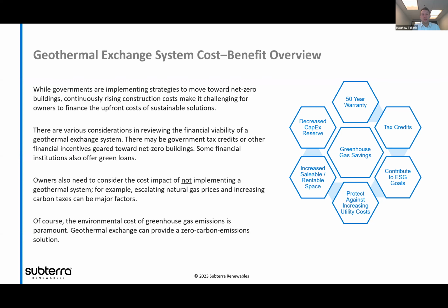When we're talking about the competing HVAC system, we're typically talking about the plant system. That's the term we use to describe the stuff that's creating the hot and the cold, so that tends to be our package of boilers, chillers, and cooling towers. What we end up doing with the geosystem, to state it simply, is remove those components, and instead we drill into the ground and put a heat pump based system in, making that plant equipment replaced by the geothermal loops. Generally, the CapEx tends to be about 1.5 to 1.75 times more than the competing HVAC system.